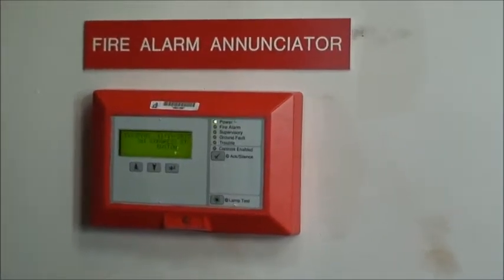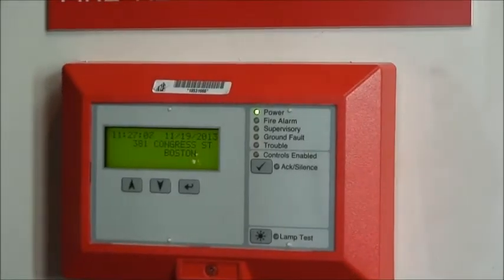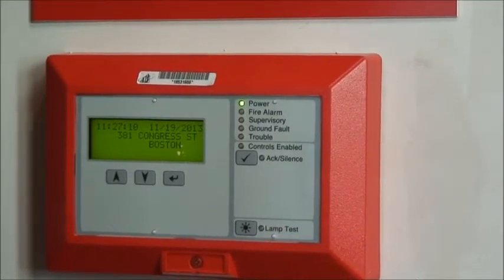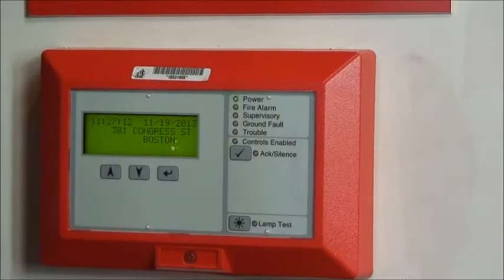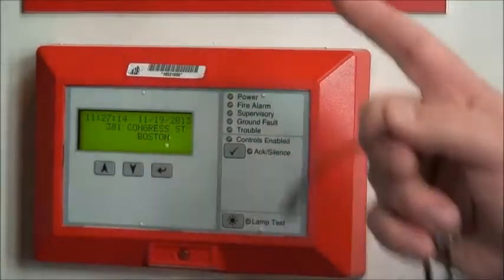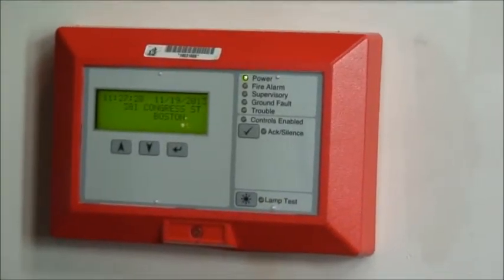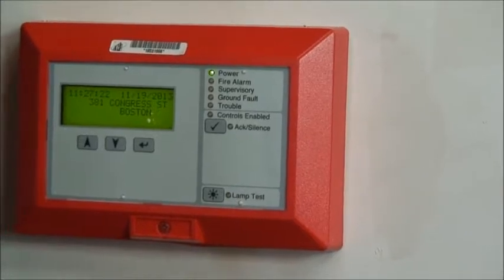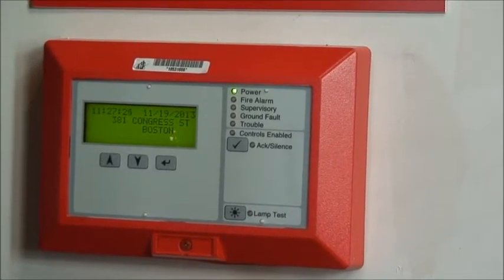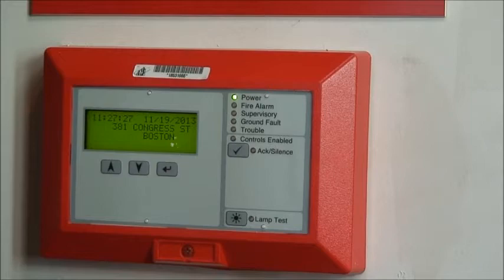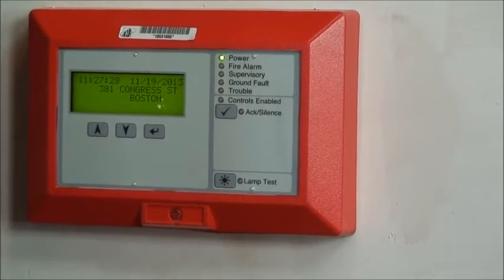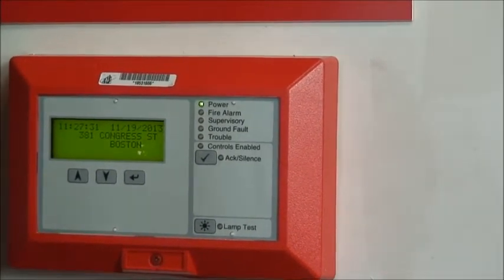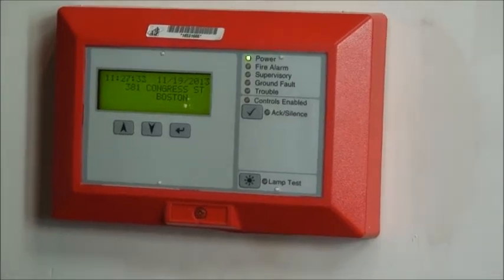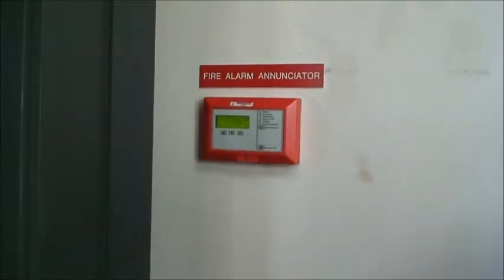You'll get an alarm from the restaurant, obviously you know that from last night. And it will indicate right here. It'll say first floor, pull station, front entrance, and then it'll give you the address. So we'll know what device went off. Okay? Good? Yep. Go to second floor.